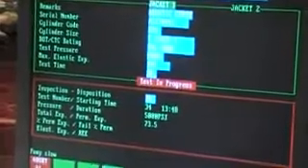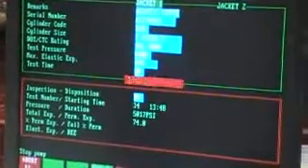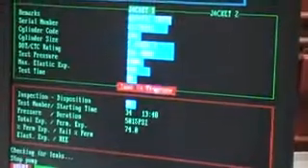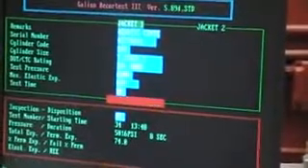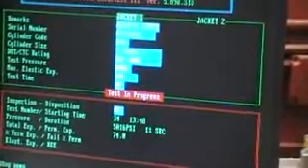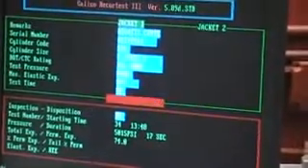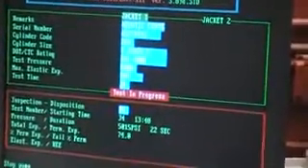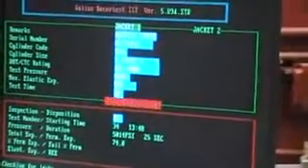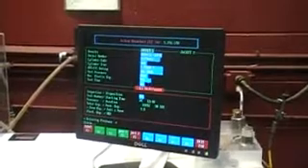So it'll go beyond 5,000 psi, or? Yes, this is because of the type of the cylinder here. We're overshooting a small margin. Your test pressure is a minimum prescribed test pressure. So 5,000 is the bare minimum that it can be held at for the test interval. It can go as high as not to exceed 10% over 5,000 psi. So there's a window in there. Should there be a problem with the test machine, I would be able to retest the cylinder after repairing the machine.